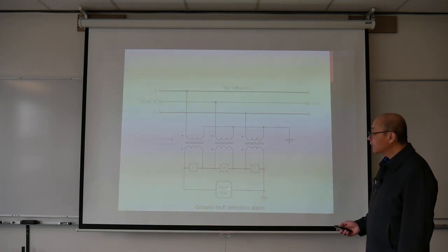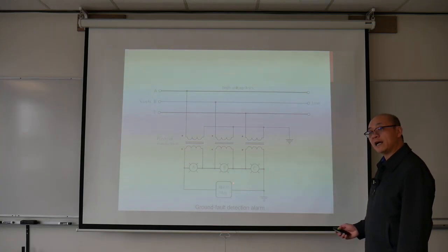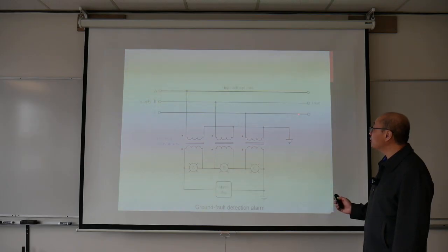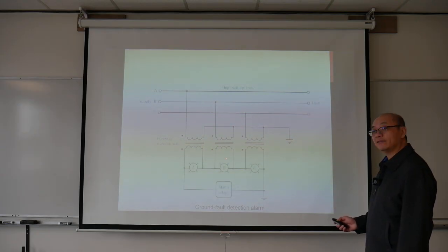The alarm relay is connected across the three potential transformers in the delta closure test way. When the three potential transformers all have an equal amount of voltage on the secondary side, this alarm relay sees 0 volts, because the closure test for a normally wired delta is 0. But if one of the lines grounds, so there's a connection between this line and the grounding point on the primary side, the Y point, then one of the potential transformers will receive 0 volts on the primary side, but the other two will see the line voltage across them. Because they now see the line voltage, the secondary voltage is increased by √3. Those two lamps become brighter, but the grounded one's lamp goes off.